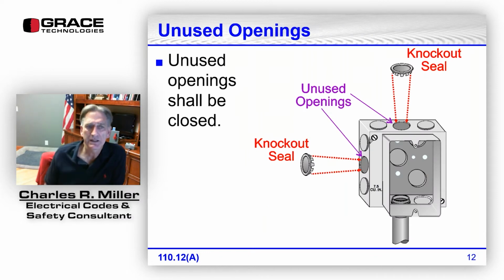110.12(A). This one is for unused openings. Unused openings should be closed. Just a good general statement. Unused openings should be closed. Now, a few editions back, they did add some other provisions, so that every opening in a box did not have to be closed. We'll get to that in a minute.